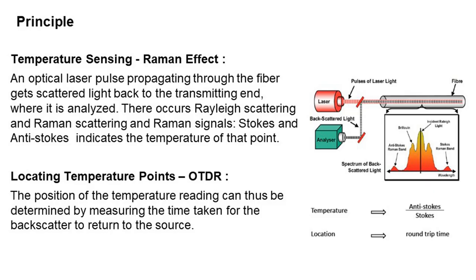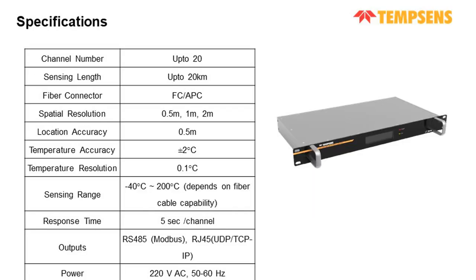This is done using the method called optical time domain reflectometry, or OTDR. When the laser pulse is sent into the fiber, we measure how long it takes for the backscattered light to return to the source. Since the speed of light in the fiber is known, this time delay tells us the exact position along the fiber where the scattering is happening, and therefore where the temperature measurement took place. This combination of Raman scattering and OTDR enables continuous temperature profiling along kilometers of optical fiber, providing real-time distributed thermal monitoring with pinpoint accuracy.